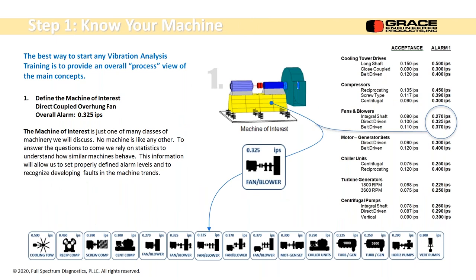This is where we start. We need to know our machine. This machine is an overhung direct coupled fan. On my list of different types of machines, this is an acceptance criteria, this is an alarm value. All these are statistically set. I would grab a bunch of reciprocating compressors, look at all their overall amplitude levels, take the mean plus three sigma and get an effective alarm level for that machine, and do that same exact thing with all of these different types of units.